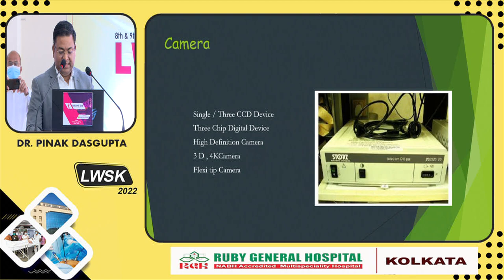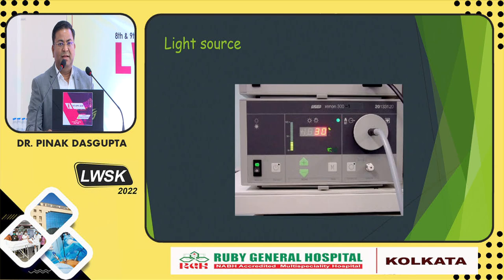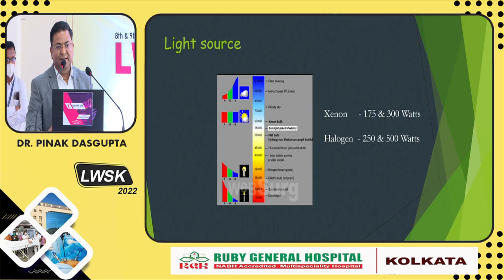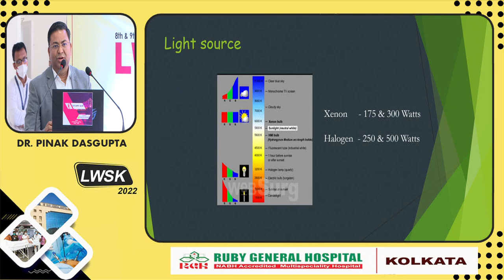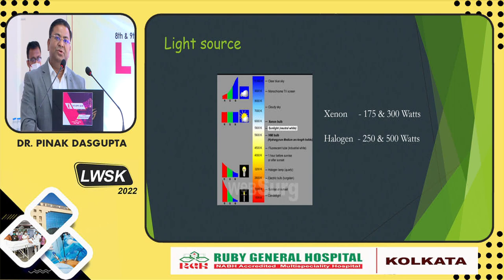For the light source, previously halogen was used, but that's no longer common now; mostly it is xenon or LED cold light source. Light is very necessary, especially if there is some bleeding inside. Without a good light source, it will be dark and you'll be forced to convert, which becomes frustrating and stunts your journey to advanced laparoscopy. So you should always have a good light source.